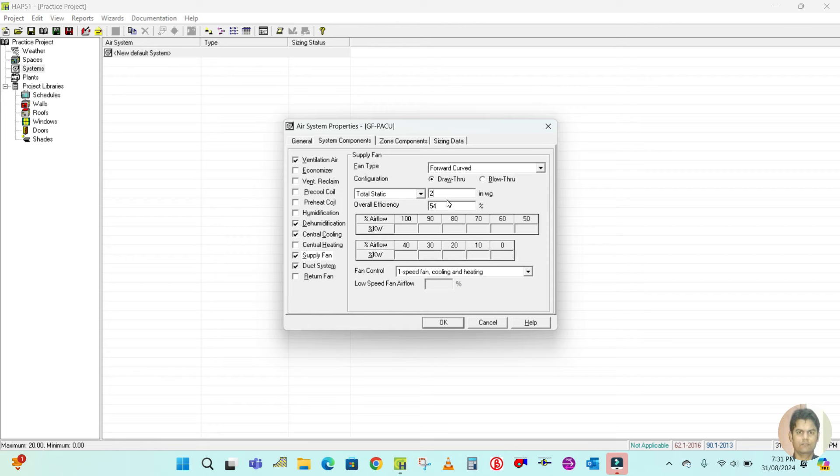Then for supply fan, you can select forward curve, draw through, or blow through — whatever is applicable. I mostly select draw through. Total static — this is the motor capacity heat generated by the blower fan motor — you should keep it at 1.5 to 3.5 inches WG. I'm going to keep it at 2.5 inches of water gauge.